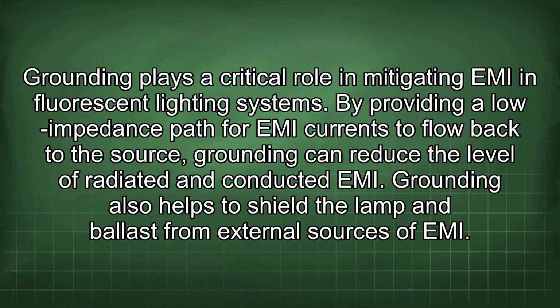Grounding plays a critical role in mitigating EMI in fluorescent lighting systems. By providing a low impedance path for EMI currents to flow back to the source, grounding can reduce the level of radiated and conducted EMI. Grounding also helps to shield the lamp and ballast from external sources of EMI.